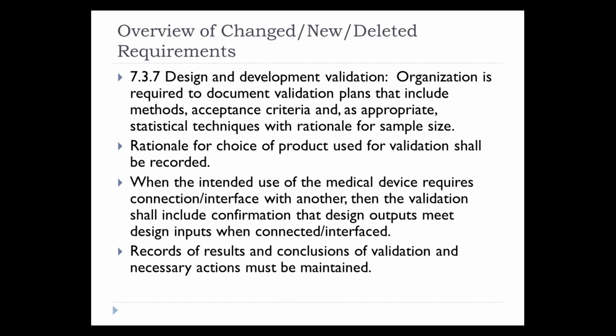7.3.7, design and development validation. You have to document the validation plans, including your methods, acceptance criteria, and as appropriate, techniques used with rationale for sample size. You need to record your rationale for why you chose a specific product for validation. And similar to verification, if the intended use of the device requires connection or interface with another, validation has to take place that way. And records of the results of validation activities, including any conclusions drawn and necessary actions to be taken, have to be maintained.